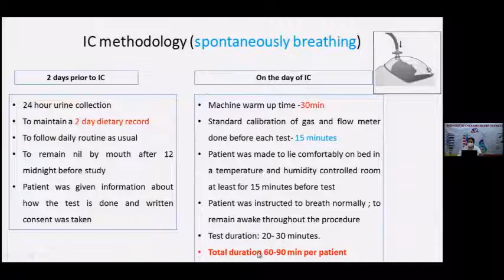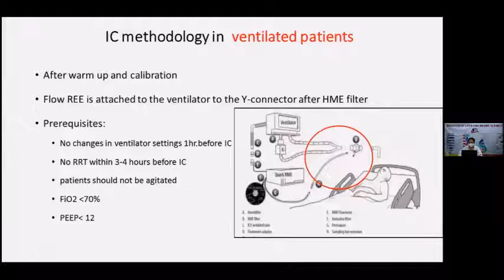Similarly, in a ventilated patient, we do it after warm-up and calibration as usual. There is a tube called the flow REE, which is attached to the ventilator at the Y connector after the HME filter. We have to make sure certain prerequisites are met for reliable results. That is, no changes in ventilator setting 1 hour before indirect calorimetry, no renal replacement therapy within 3 to 4 hours before IC, the patient should not be in an agitated state, FiO2 should be less than 70%, and PEEP should be less than 12.